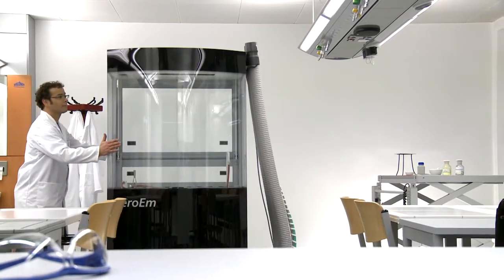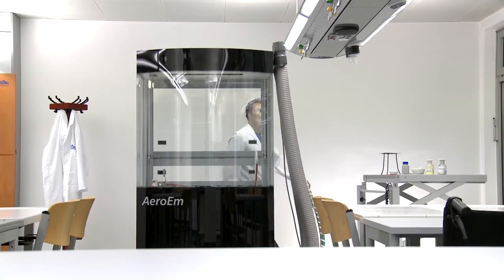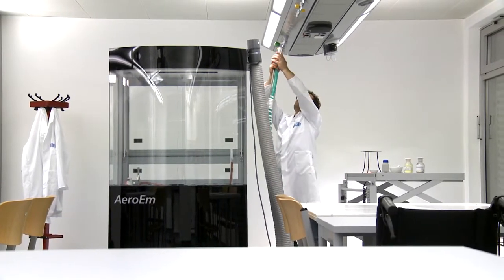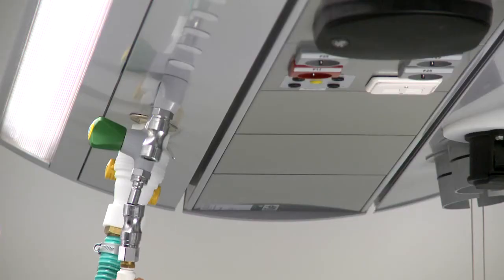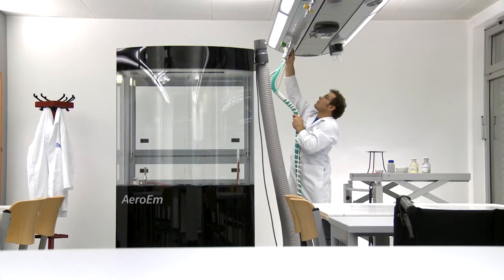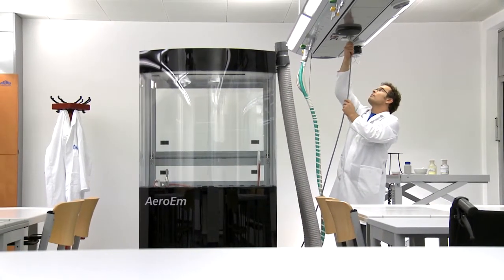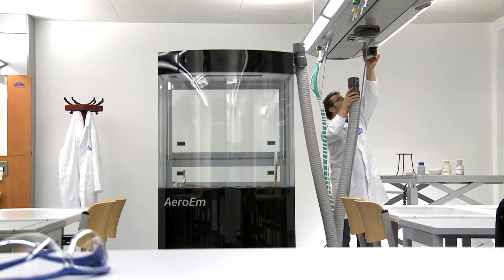The Aero EM from the Scala Modular System is a full-feature mobile fume cupboard which complies with all the requirements of the DIN EN 14175 standard. Aero EM can be positioned freely in the room and connected to the service wing using plug-in connections. Variant 3 of the service wing offers you the opportunity to operate the mobile fume cupboard in a wide variety of locations in the laboratory.